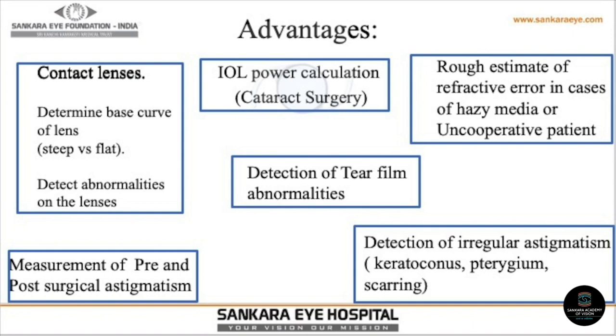The advantages and uses of the manual keratometer include: IOL power calculation for cataract surgery; contact lens fitting to determine the base curves for RGP or soft hydrogel lenses; detecting abnormalities over contact lenses; follow-up of long-term contact lens use to check for changes in radius of curvature; measuring pre- and post-surgical astigmatism after graft or cataract surgery; detecting tear film abnormalities via distorted mires, in which case a drop of lubricant is applied and keratometric values rechecked; and providing a rough estimate of refractive error in cases of hazy media or in uncooperative patients.